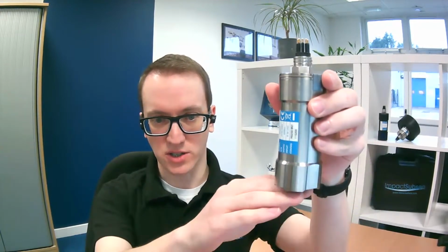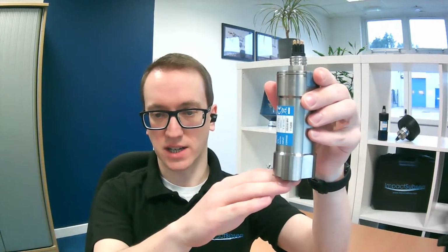For that reason, we put in a second detection mode called strongest echo. If you use the strongest echo detection mode, it sends out the acoustic pulse as before, travels through the water, hits the seabed and comes back again. But this time, the ISA 500 listens to every single echo that comes back, so it gets a large echo off the seabed, and any smaller echoes off a fish, marine growth, or anything else in the water column. It picks out the echo with the largest amplitude, which will almost certainly be the seabed, and uses that to derive distance to the seabed.